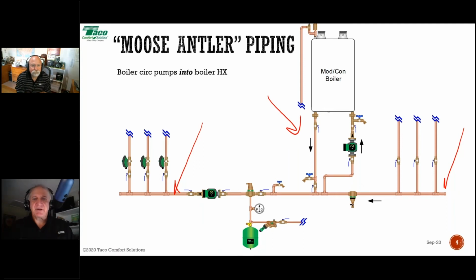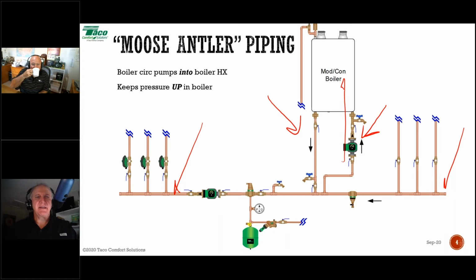A couple of key things right here. Your boiler circulator always pumps into the high head loss heat exchanger. That keeps the pressure up in the boiler, and for very good reason. If we pumped away from that heat exchanger, we might drop the pressure in the heat exchanger. And when that boiler fires up to high temperature to make domestic hot water, it is conceivable that that boiler could flash to steam, and it'll make a hell of a racket. The good news is it won't do it for very long, but the bad news is we've got nothing left. So always pump into that high head loss heat exchanger.